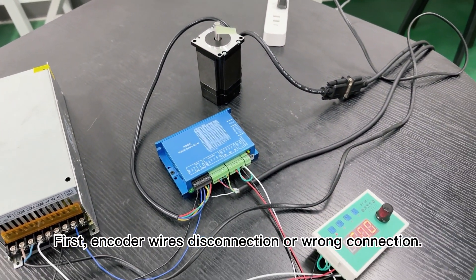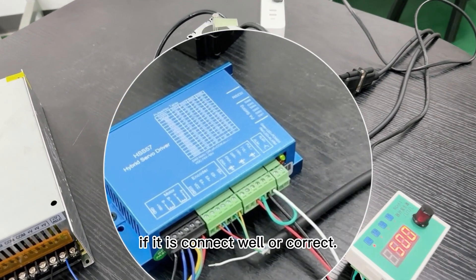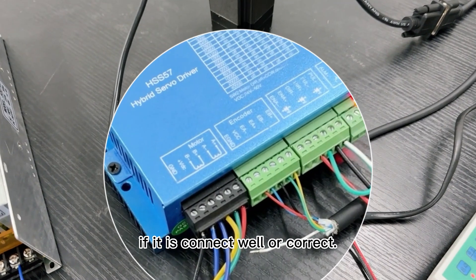So check your encoder wire. If disconnected, the wire or incorrect, look at this: the encoder wire is loose and also the encoder wire order is wrong.